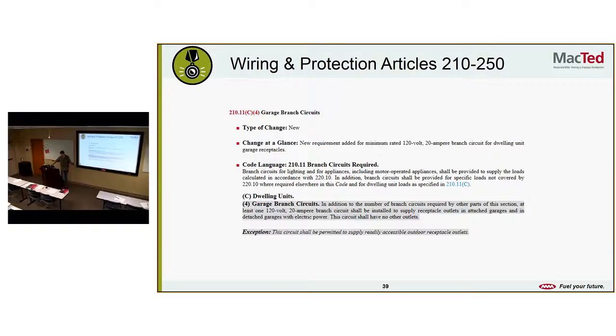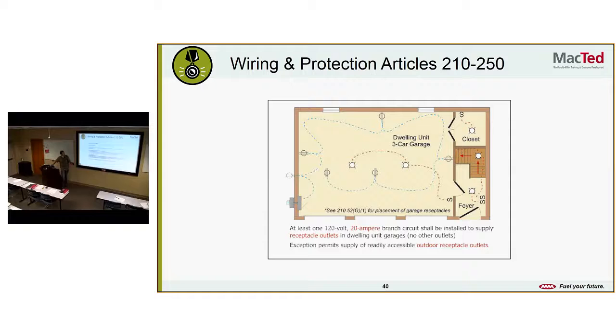Garage branch circuits, new requirements added for minimum rated 120 volt, 20 amp branch circuits for dwelling unit garage receptacles. So this applies to our houses. Branch circuits for lighting and appliances, including motor operated appliances, shall be provided to supply the loads calculated in accordance with 220.10. Branch circuits shall be provided for specific loads not covered in 220.10. So it says, looks like our change is, in addition to the number of branch circuits required by other parts of the section, at least one 120 volt, 20 amp branch circuit shall be installed to supply receptacle outlets in attached garages and detached garages with electric power. This circuit shall have no other outlets. So if you're building a house, that'd be good to know.